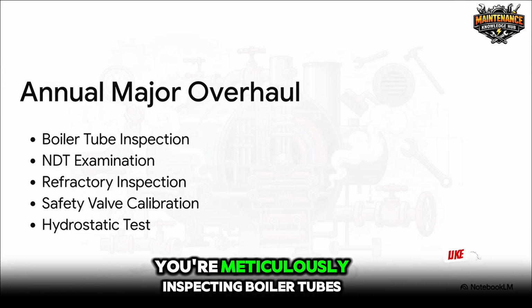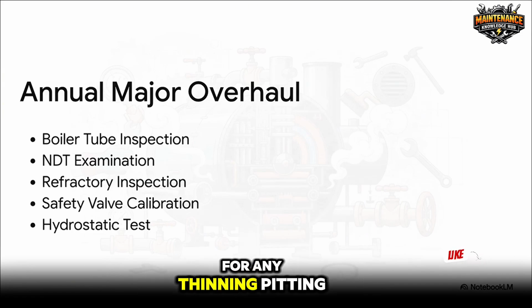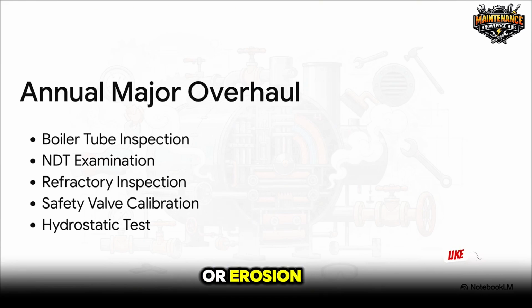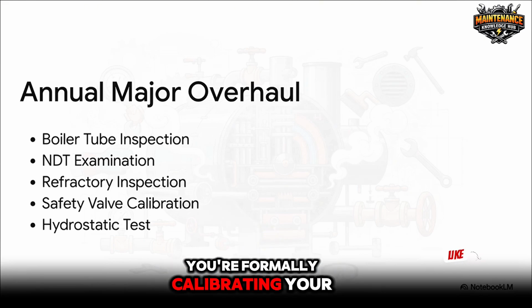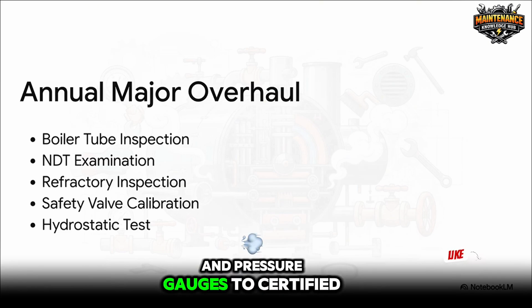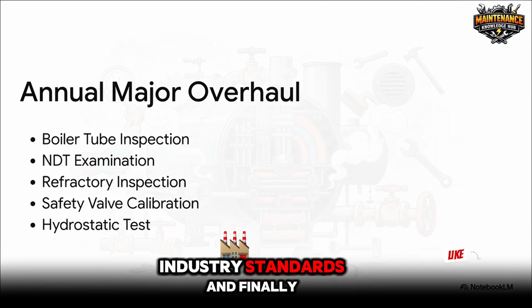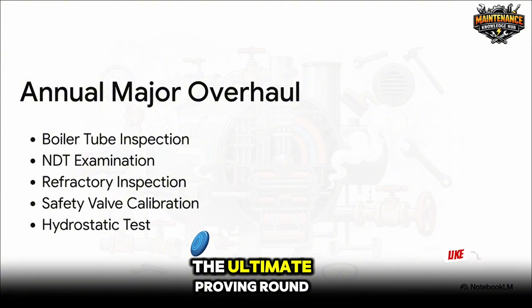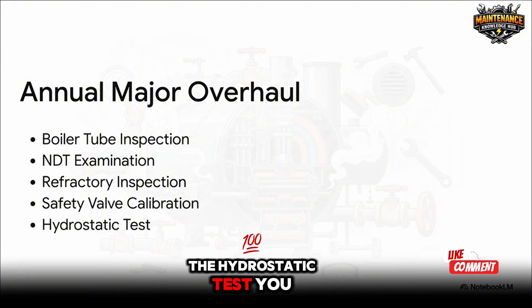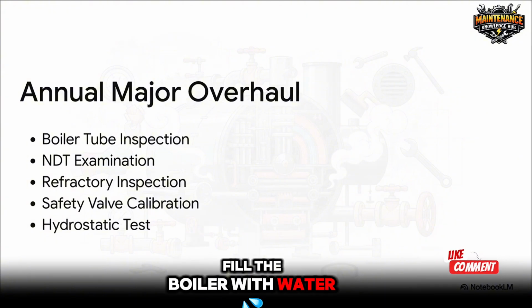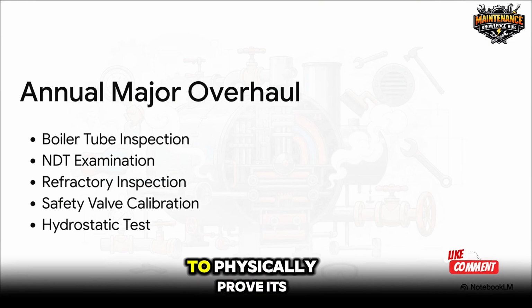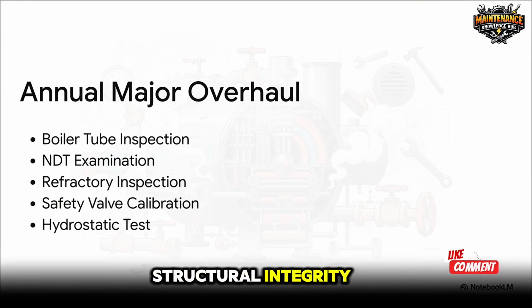You're meticulously inspecting boiler tubes for any thinning, pitting, or erosion. You are repairing cracked refractory linings. You're formally calibrating your safety valves and pressure gauges to certified industry standards. And finally, the ultimate proving ground, the hydrostatic test.